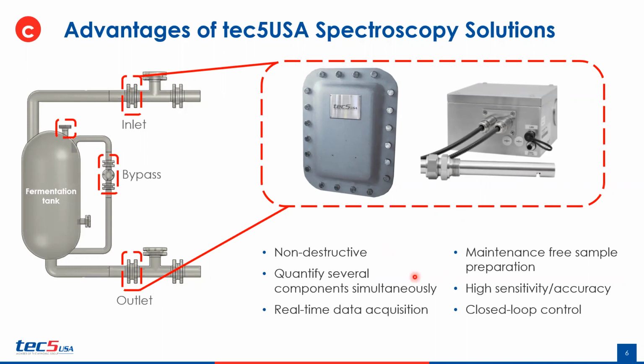It also quantifies several components simultaneously. If you're looking in a wide spectral range, in the near IR range for instance, you have a few different key regions that are associated with various components, and pinpointing those different regions allows you to quantify multiple components with a single measurement. It also allows for real-time data acquisition. These measurements can be performed on the order of milliseconds to seconds, so the data you're getting in real time is significant to what you're actually looking at in your process. Because of this seconds-to-minute measurement, you can make real-time decisions based on the results.